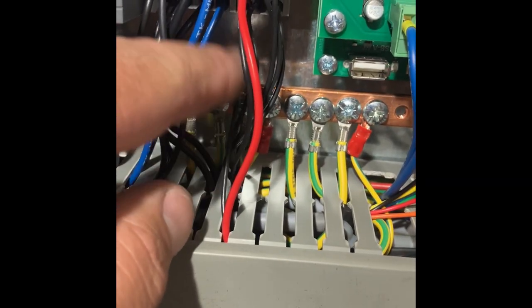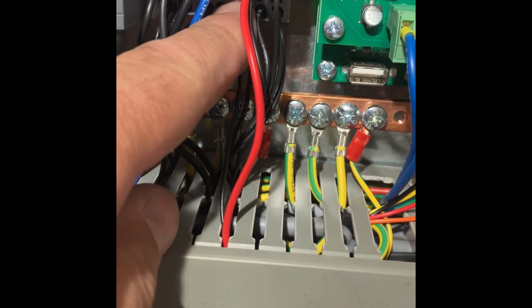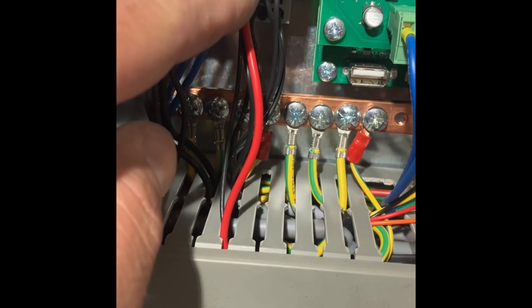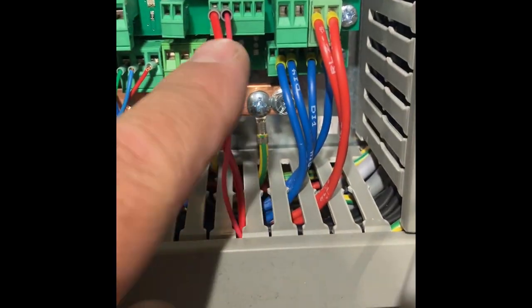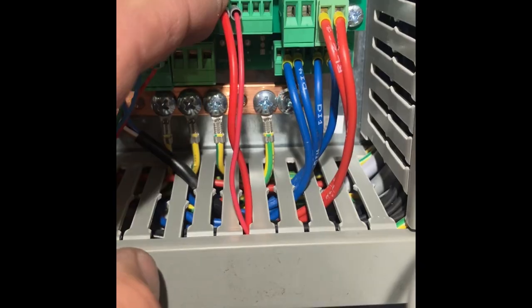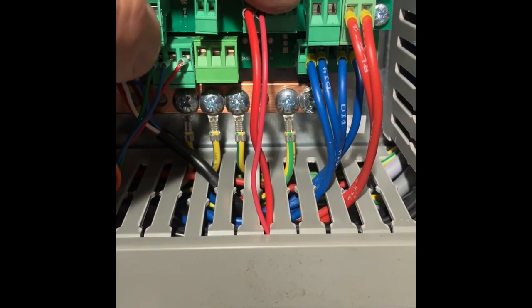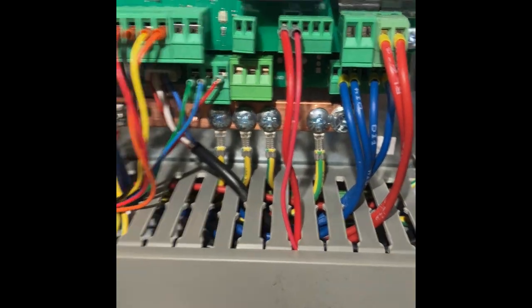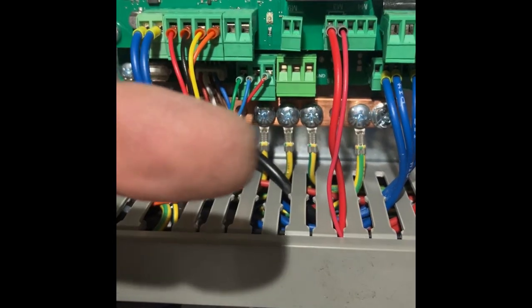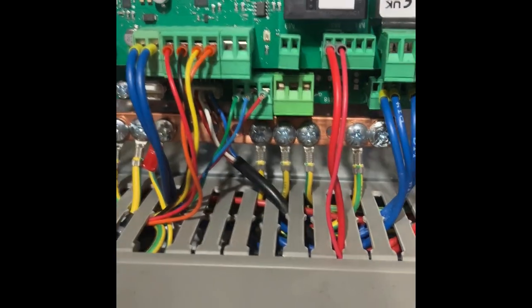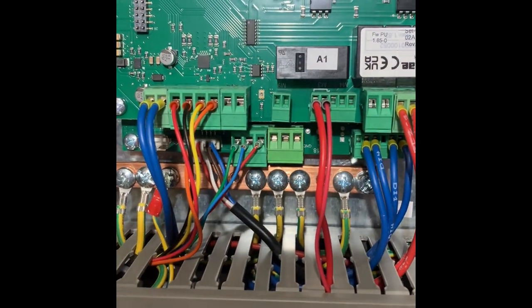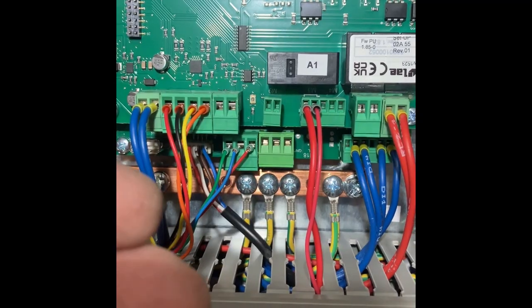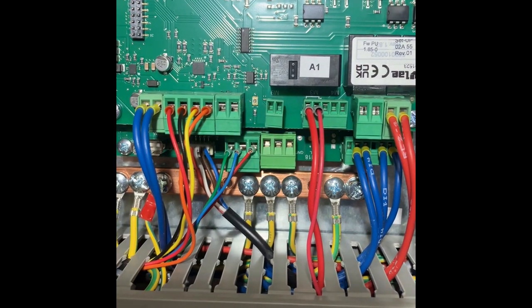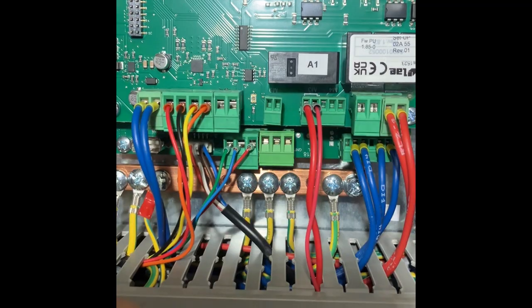My neutral wire here that's going to the Aero is just tied directly in with their neutral wire. I took the hot here, the 24 volt hot, and I looped it down, brought it into the common on the alarm contacts, and then this wire is in the same cable with this other black wire over here, and those go right over to the Aero. So if this dryer were to fault out, you will get a full 24 volt hot and neutral feeding into the Aero, not your standard DI loop that we think of.